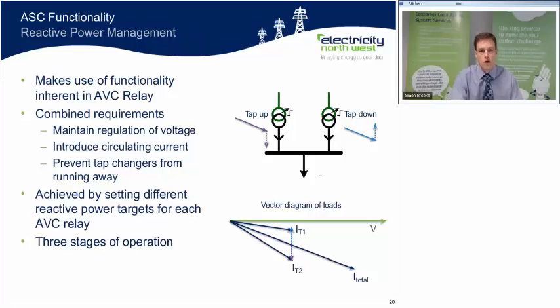So to introduce the circulating current that we require, if you look at the vector diagram on the lower right, we'll see the overall load provided by the substation and then the individual currents in the two transformers, T1 representing the transformer on the right and T2 the transformer on the left. And you'll see the dotted line vectors which represent the circulating current. So what we do is we give a reactive power target to the AVC relays that encourages them to change their tap position to deliver this circulating current. And during this period, effective voltage regulation is maintained.